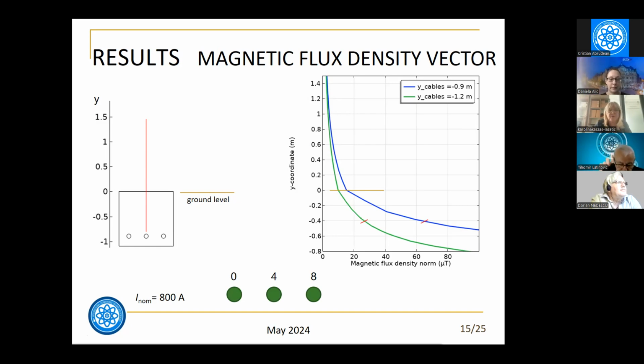And because the soil has some magnetic permeability, we have this change in the direction of the magnetic field, and we can see, for instance, at the depth of 0.4 meter, when the cable is deeper, the magnetic field value is lower than in the other case when the cable is closer to the ground level.